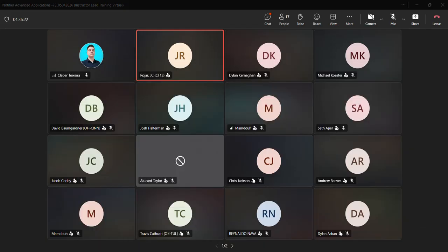Like I said, it's pointing to the devices, not to the panel. So play the following message. It's an evac message on the 2nd, 3rd, and 4th floor speakers if either the smoke detector or pull station on the 3rd floor is in alarm. Play the following message, which is the alert message, on the floors that are not being evacuated when number 1 is triggered. So number 1 and number 2 have to do with one another. One's an evac, one's the alert. You guys already did that in the last lab, so it looks like it's just having you repeat that, kind of, but they want you to put the messages together.